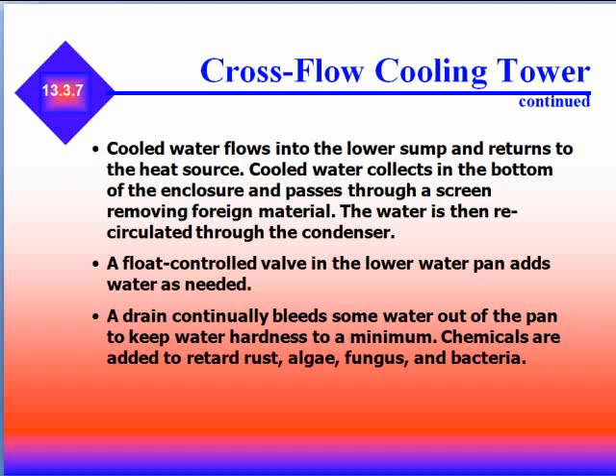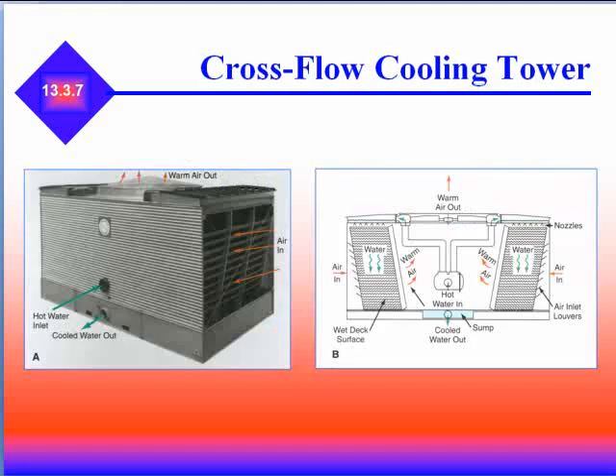A float-controlled valve in the lower water pan adds water as needed. A drain continuously bleeds some water out of the pan to keep water hardness to a minimum. Chemicals are added to retard rust, algae, fungus, and bacteria.